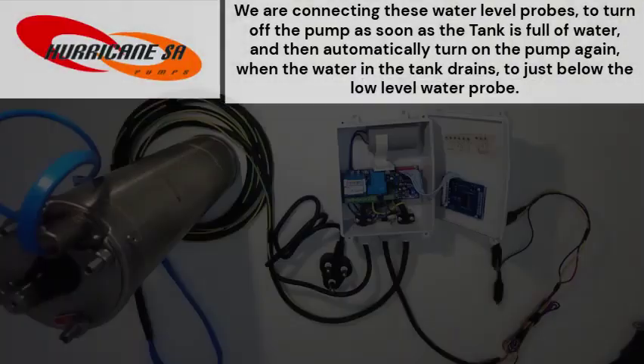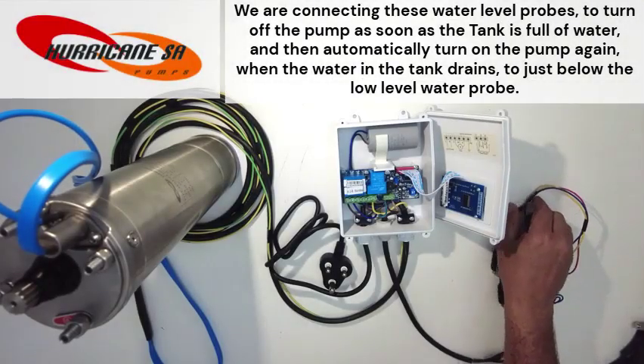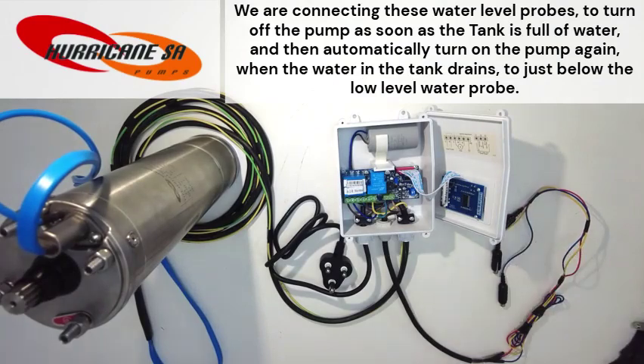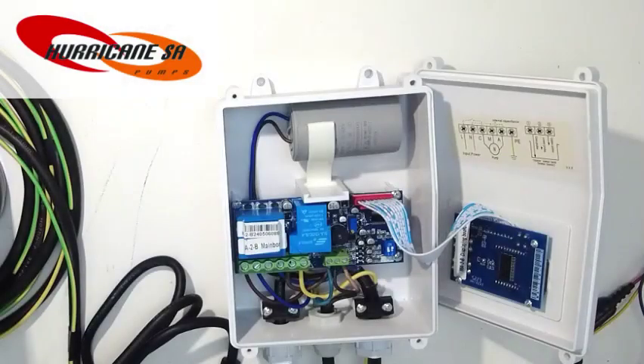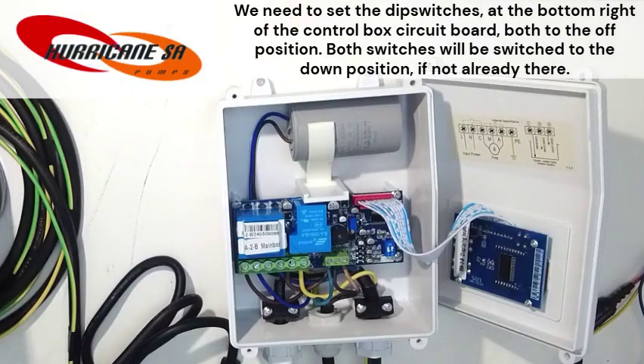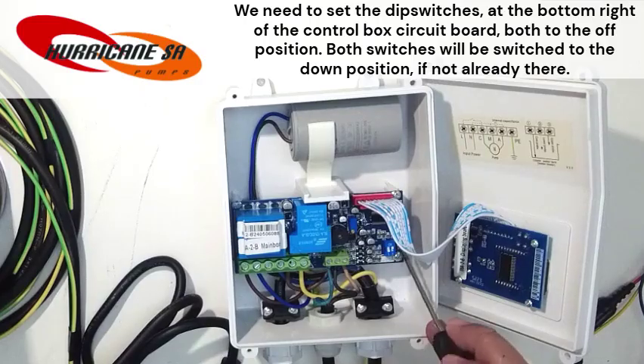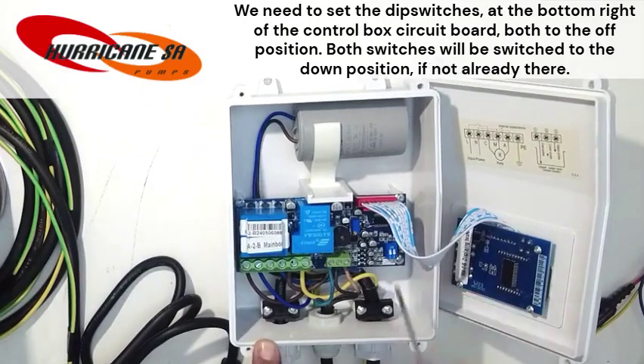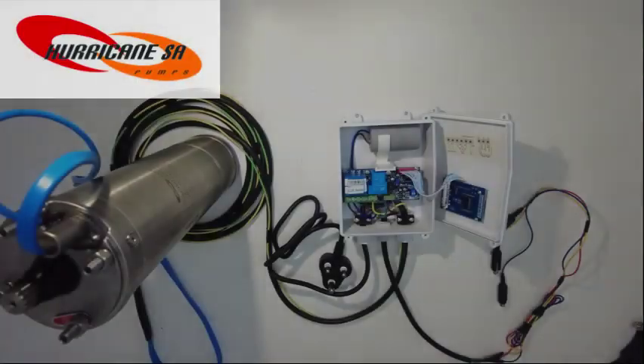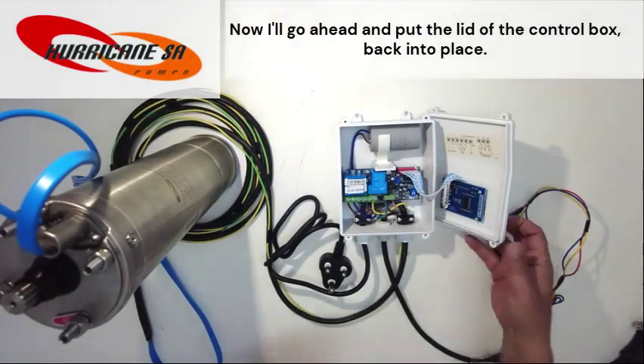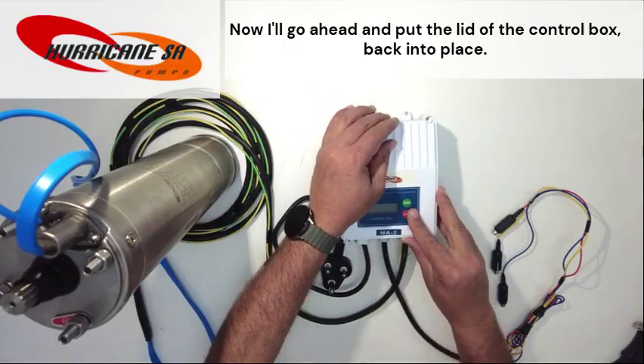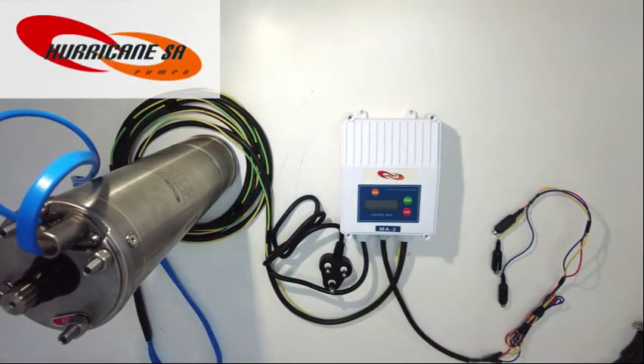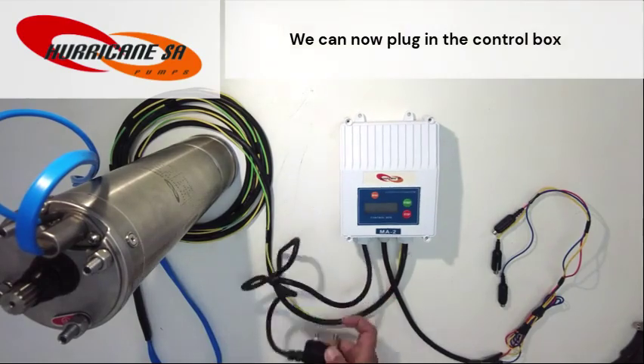We are connecting these water level probes to turn off the pump as soon as the tank is full of water, and then automatically turn on the pump again when the water in the tank drains to just below the low level water probe. We need to set the dip switches at the bottom right of the control box circuit board, both to the off position. Both switches will be switched to the down position, if not already there. Now I'll go ahead and put the lid of the control box back into place. We can now plug in the control box.